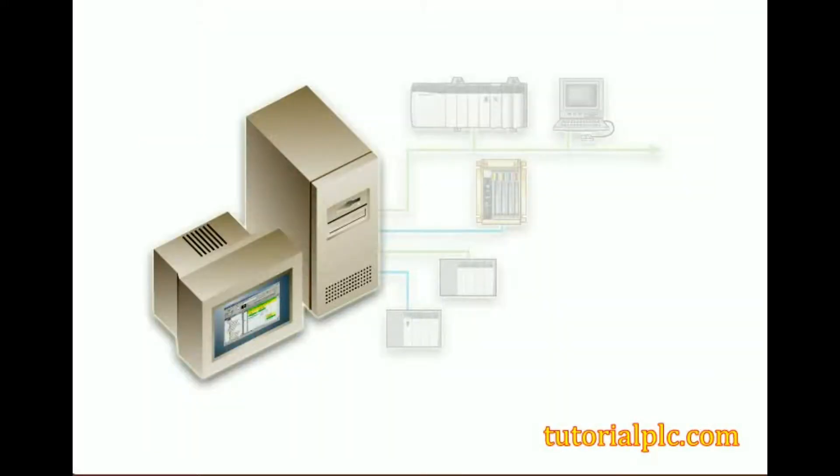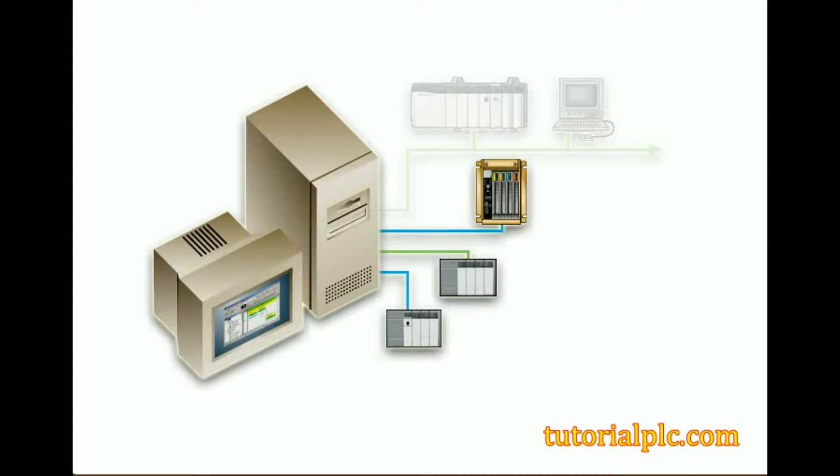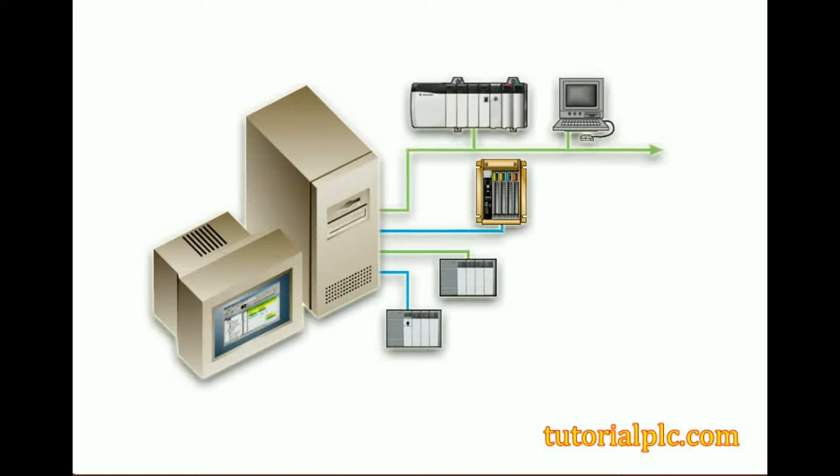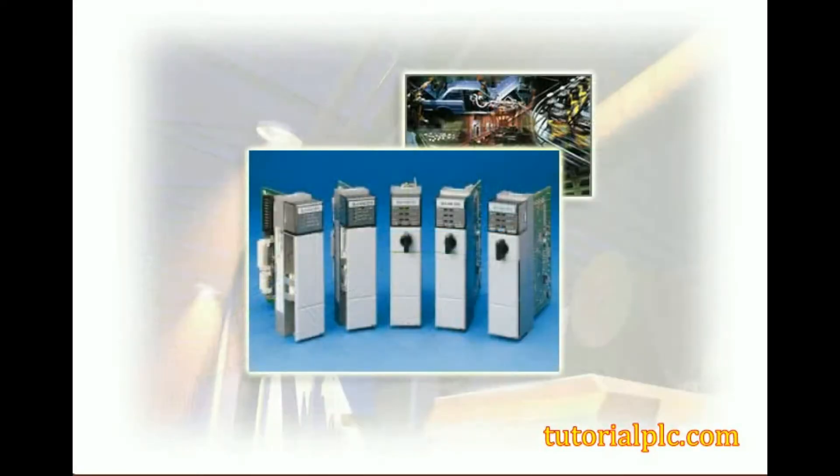We can choose from several communication protocols or methods, including RS-232 or serial communication, DH-485, DH-plus, and Ethernet. Our application requirements and the type of SLC 500 processor being used determine the communication methods we can use to go online.